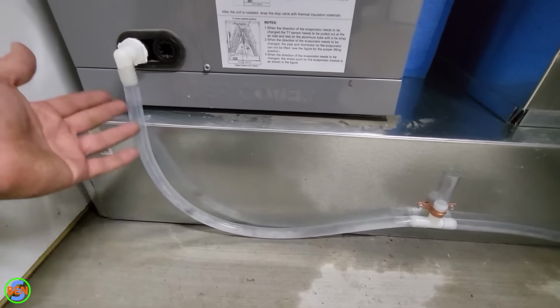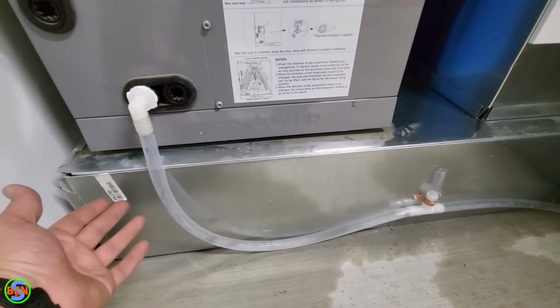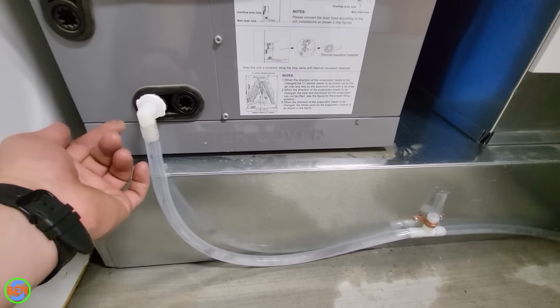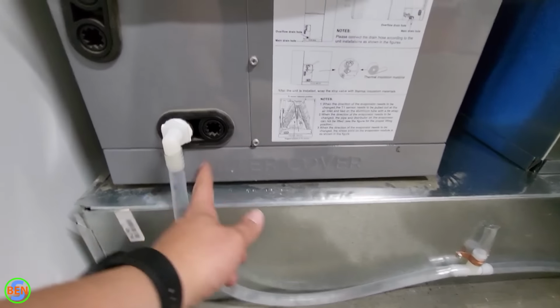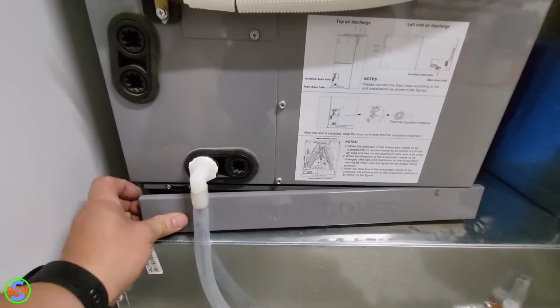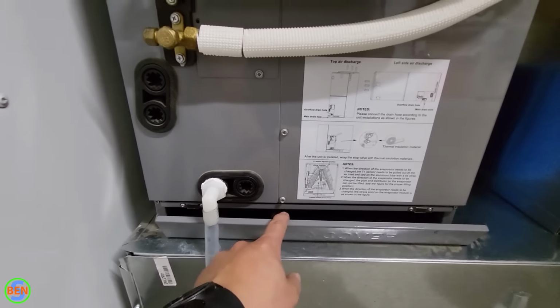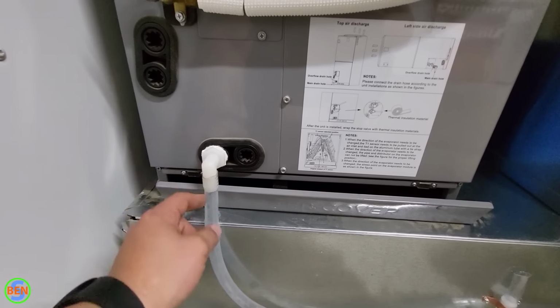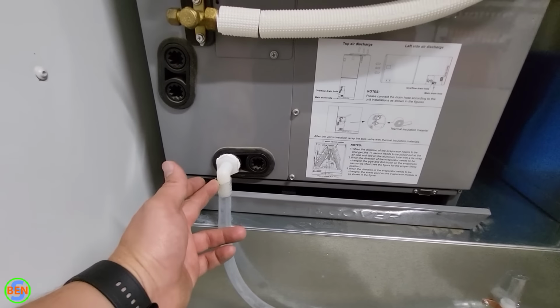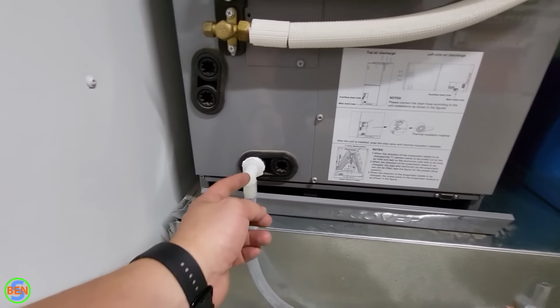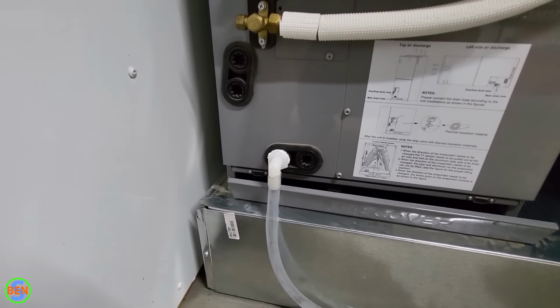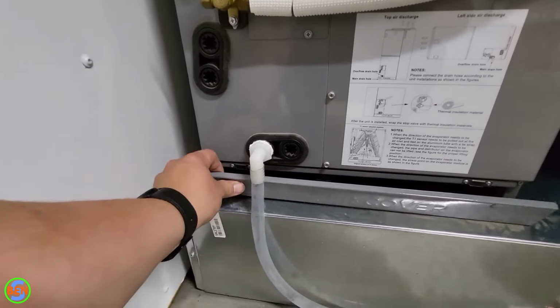Like I said, you can do this with 3/4 inch PVC if you prefer to do it that way. But the other benefit that we have in this situation is that since the air filter is right here, to be able to remove this and replace it, we're going to have to just pull this vinyl hose off of here. So it's going to work just fine in this situation. If this were rigid PVC, we'd have to figure out some other way to make that happen. Either make this go over and down, which could be a possibility, but this is going to work just fine. The simpler the better in a lot of ways, just for fewer places for the line to get plugged or to have issues with.